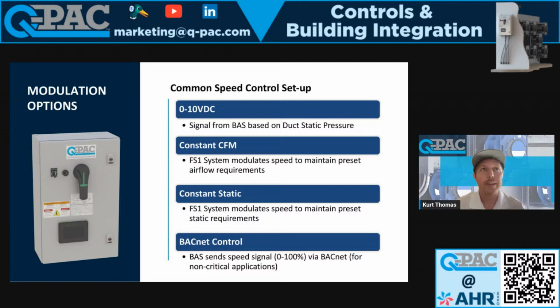So this mode is most commonly used from what I've seen in hospitals on return arrays. So hospitals have very strict requirements on how many air changes per hour they need. And so they will set the return fans to match whatever requirements they need and make sure they're exhausting enough air out of their building to maintain the correct air changes per hour. And then they'll just set the supply fan to make sure that it's maintaining the static pressure.